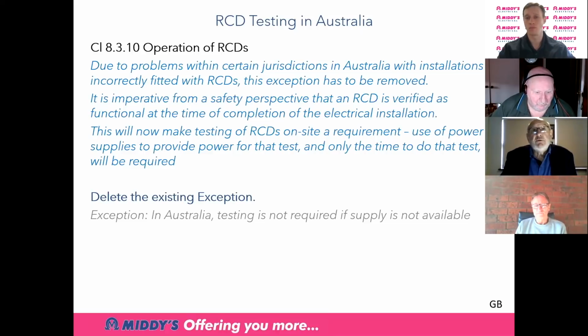The difficult part of it is that we actually added an exception for Australia, which is in grey down the bottom, that if there were no supply available, then you don't need to do your RCD testing to check that it actually works within the installation. This is a bit crazy. We've had problems with certain jurisdictions in Australia that the electricians walked away from a job and not really done the compliance check for the RCD.